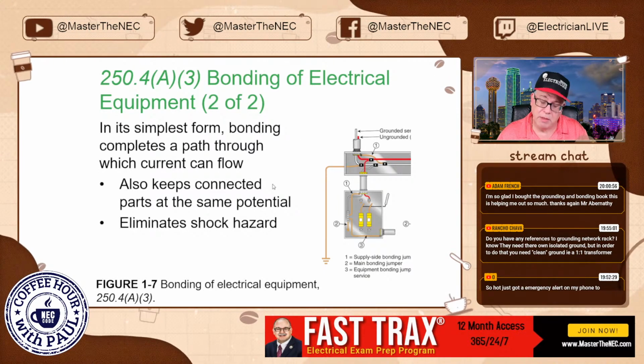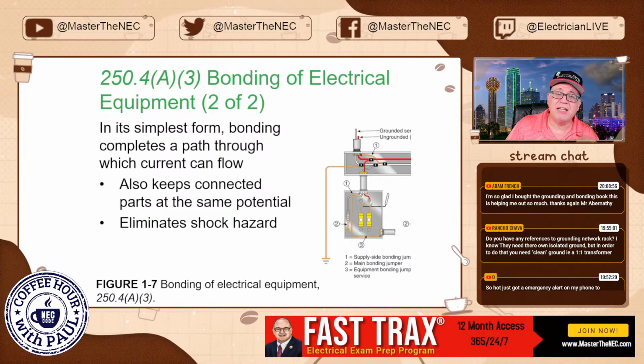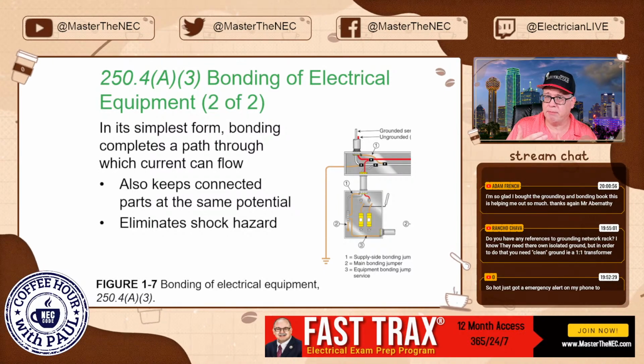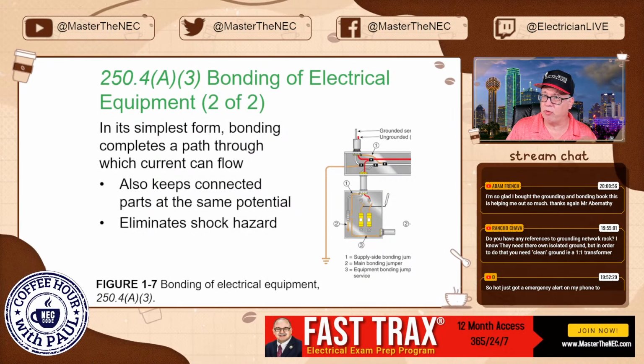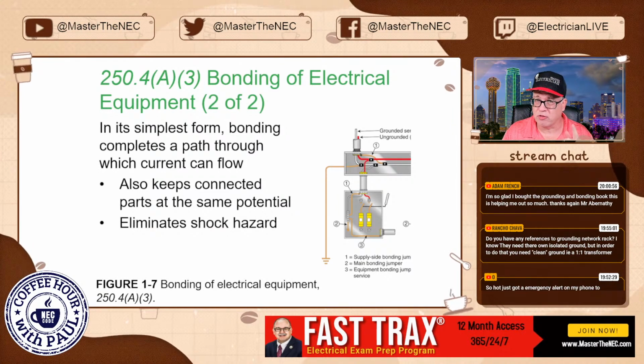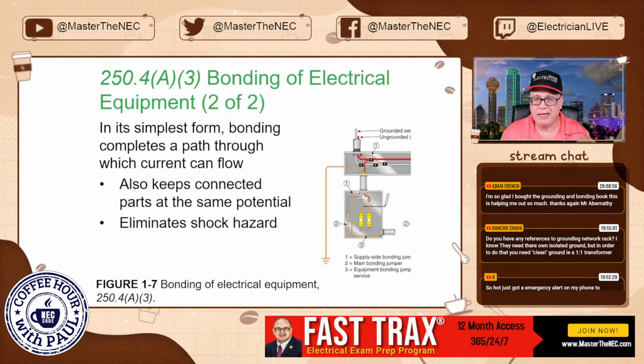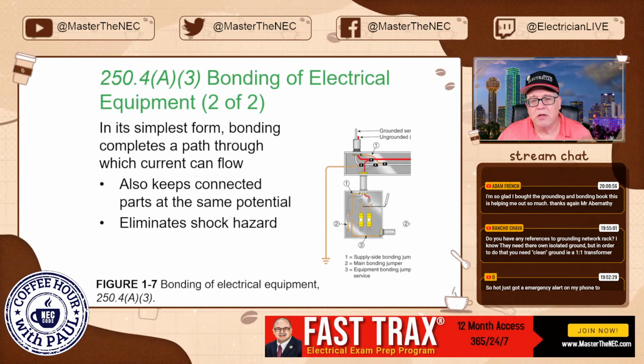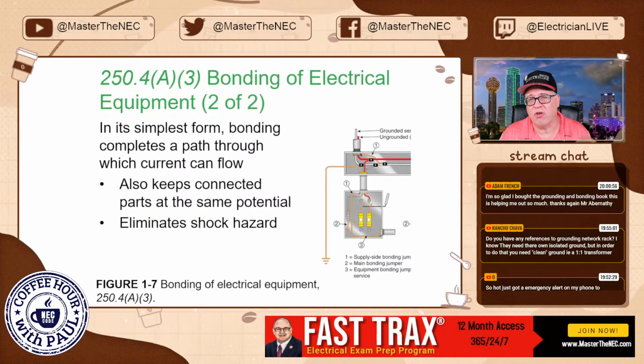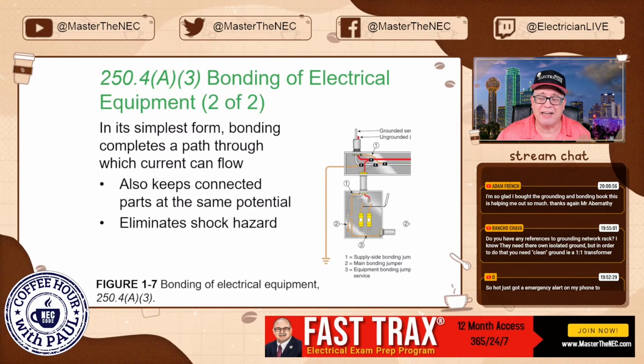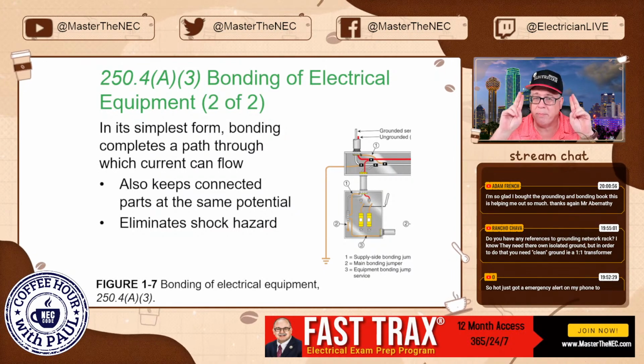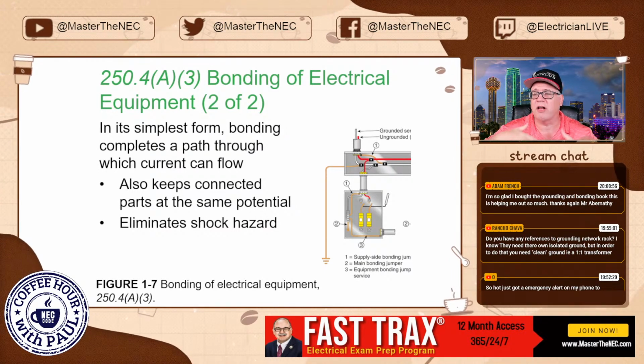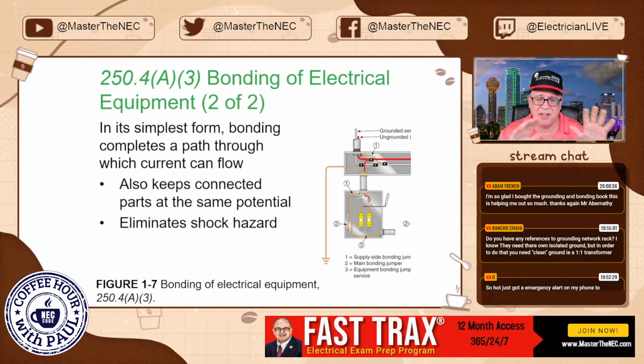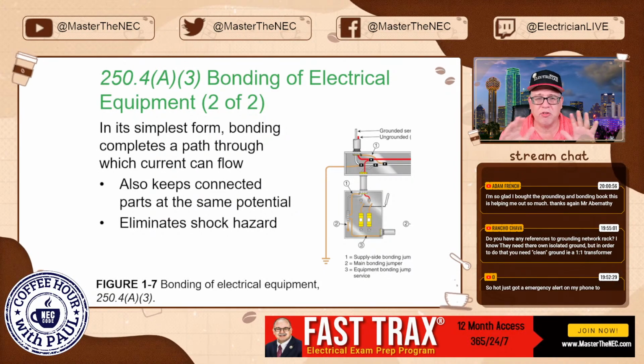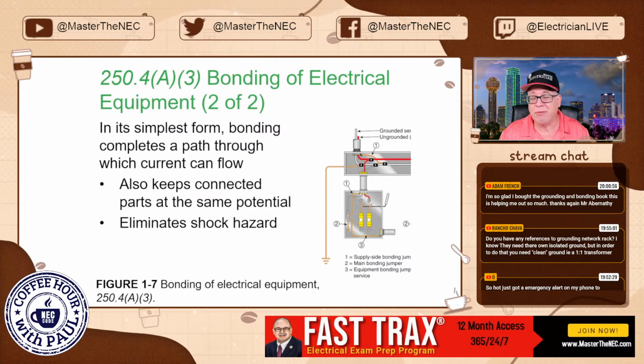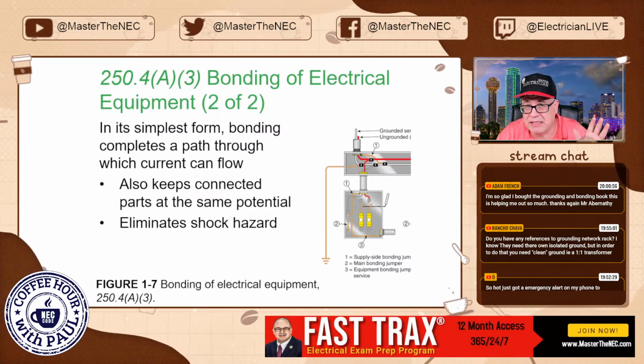All right, now with that said, it's a little more dicey upstream. As an electrician, you don't know whether there's a fuse at the transformer. You know there's probably one on the primary side, but it's nothing that you and I have to do with. So the real issue for us on the supply side, with all that bonding and the connection that permits us to connect to the grounded neutral conductor, is more or less for potential, and it does help reduce the shock hazard. Sadly, we're probably not going to clear any overcurrent device upstream.